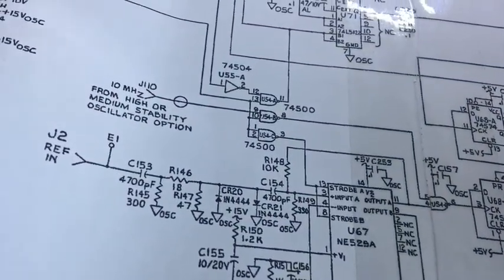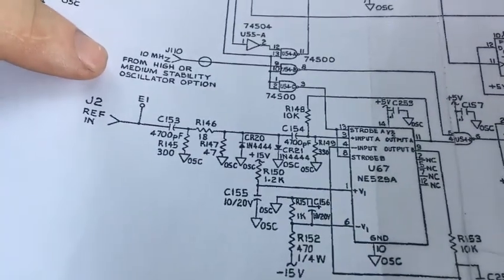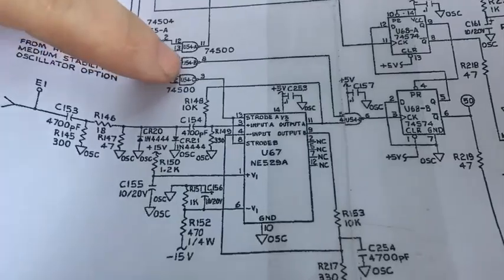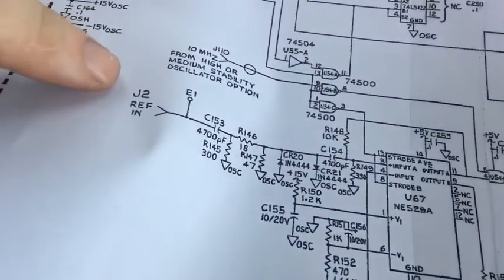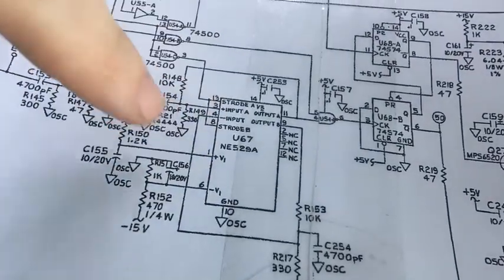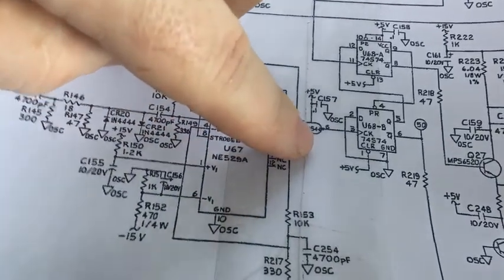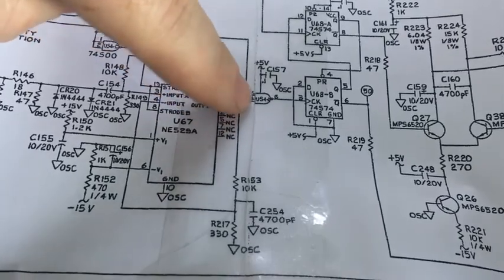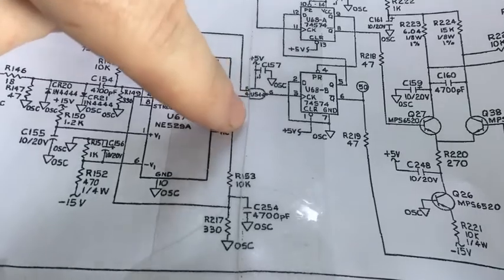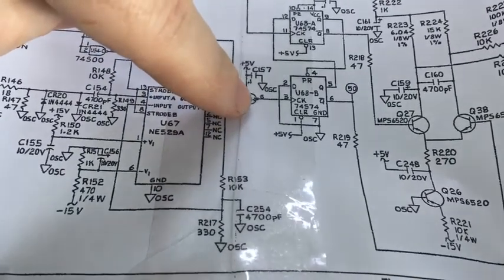Okay, so I've printed out the circuit diagrams for this thing to make it easy to look at, instead of on the computer. And tracing through the RF, the OCXO comes in here, goes through that device, which buffers it, comes through, goes to this switching NAND gate here. Over here we've got the reference input, so if you've got a reference coming from the outside with the switch on the back turned on to external, then it will come through here, goes to this device here, which is another switching thing, comes back out through to that NAND gate. So you should have 10 MHz on either of those pins, depending whether you've got internal or external reference going on. Then you should get 10 MHz coming out of this one, and I'm not getting that.